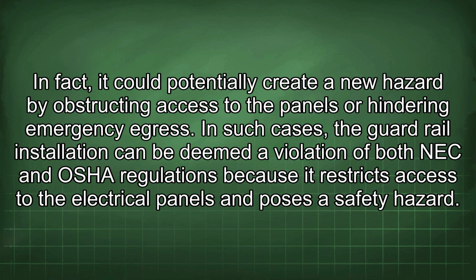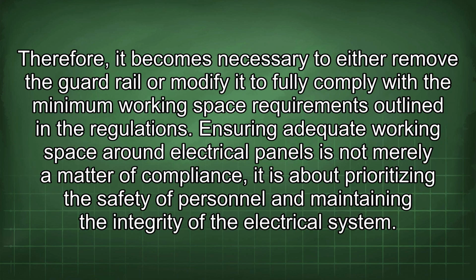In fact, it could potentially create a new hazard by obstructing access to the panels or hindering emergency egress. In such cases, the guardrail installation can be deemed a violation of both NEC and OSHA regulations because it restricts access to the electrical panels and poses a safety hazard. Therefore, it becomes necessary to either remove the guardrail or modify it to fully comply with the minimum working space requirements outlined in the regulations.